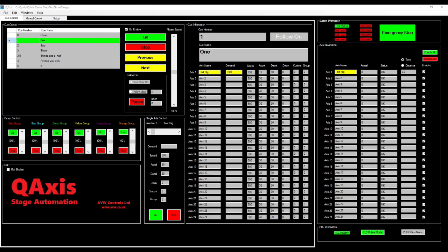So this is the HMI for our system, Q-axis. And this is what gives the PLC all its demands, accelerations and decelerations. So at the moment we can see that over here, our actual position is at zero. And we're on Q1 at the moment with a demand of 1000. A speed of 999, which is 99.9%. An acceleration of 10, which is 10 tenths of a second. A deceleration of 10 tenths of a second, one second. So it will accelerate and decelerate quite quickly. Get to 1000 and it will do it in six seconds.